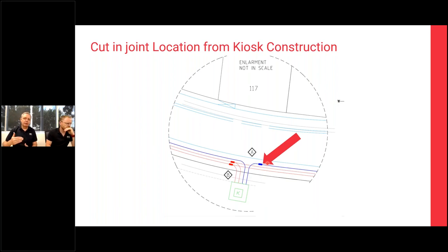So rather than going straight in there and replacing terminations for no reason, what we've done is that extra bit of work without taking anything offline. It's all online testing and located it to this particular joint here. So the company in question should be able to go in and proactively replace that joint. If you move the open point, nobody needs to be off supply, and you can do that in a controlled manner in normal working hours, and get that done and replaced before the failure occurs.